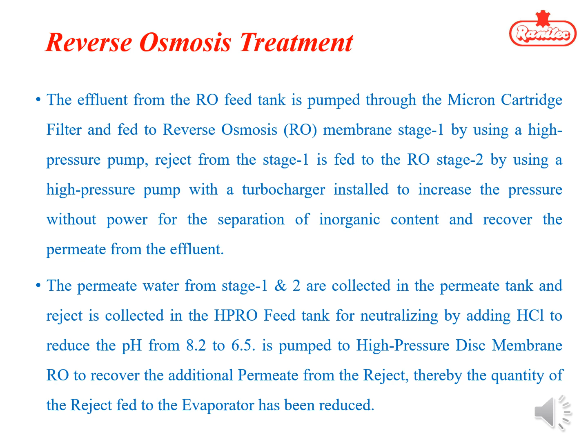The permeate water from the first stage and the second stage are collected in the permeate tank, and the reject is collected in the high pressure RO feed tank for neutralizing by adding HCl to reduce the pH from 8.2 to 6.5. It is pumped to a high pressure disk membrane RO to recover additional permeate from the reject. Thereby the quantity of reject fed to the evaporator has been reduced.